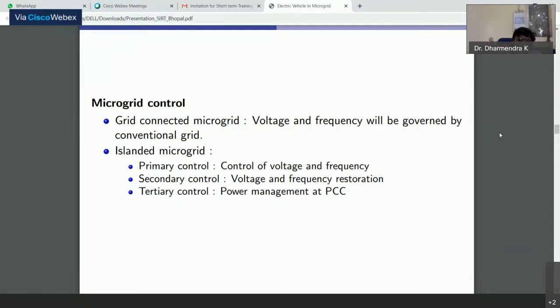So the voltage and frequency will be dictated by the primary controller. And basically, if you see the droop control operation, when the load increases, the voltage and frequency come down. To restore this voltage and frequency, the secondary control acts. Maybe after every 15 minutes, the voltage and frequency level of the microgrid will be restored to its nominal value again.